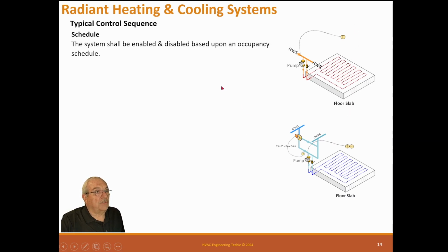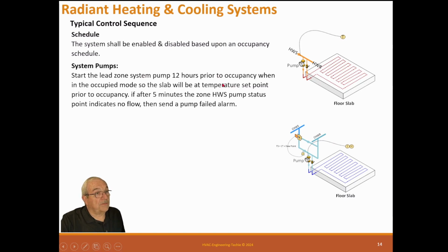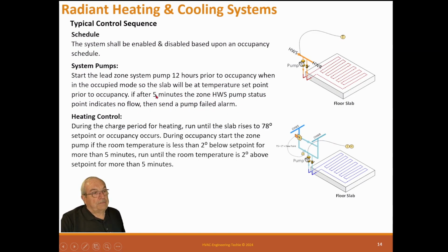So the typical control sequence: the system shall be enabled and disabled based upon an occupancy schedule. System pumps: start the lead zone system pump 12 hours prior to occupancy when in the unoccupied mode, so that the slab will be at temperature set point prior to occupancy. If after 5 minutes the zone hot water pump status indicates no flow, then it's a pump failure.